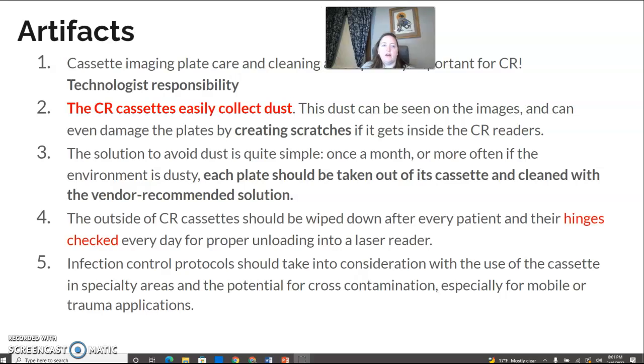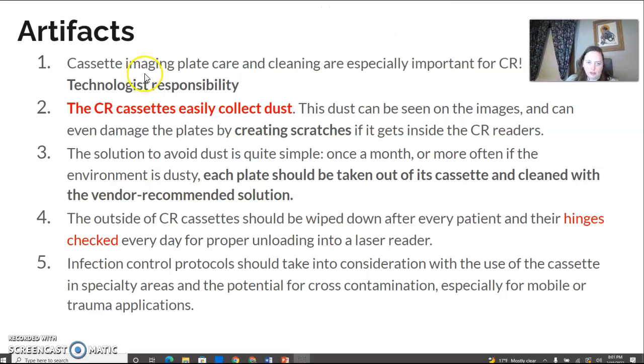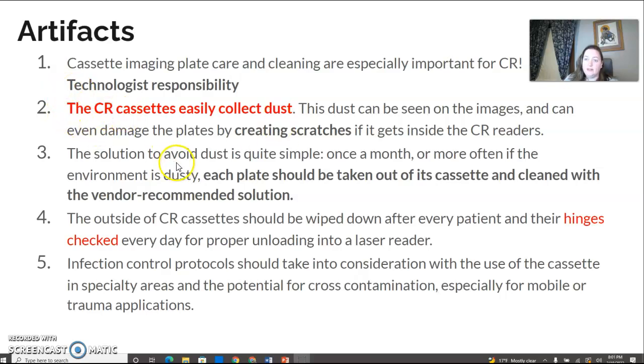Some general notes about artifacts: the cassettes and imaging plates should be cleaned. It's a technologist's responsibility — they easily collect dust. If you are somewhere that's using CR plates, make sure they're getting cleaned. We're transitioning basically to all digital, so they're just not used as much. But if you have to use one, like the scoliosis cassette which is CR, that will need to be checked for dust and cleaned.